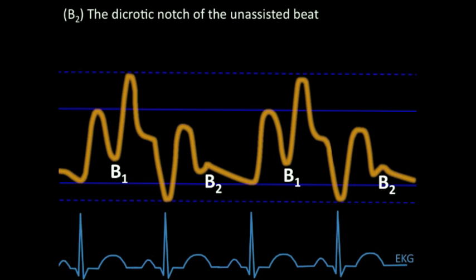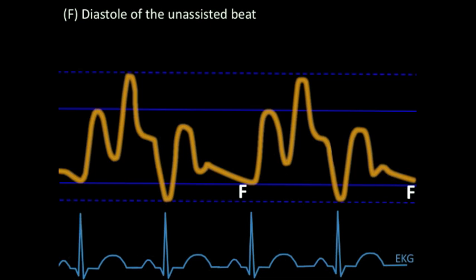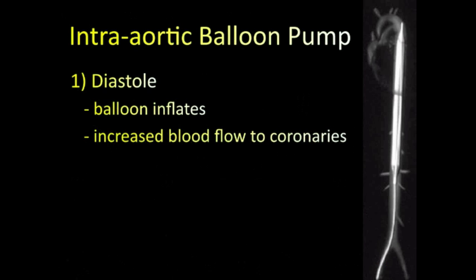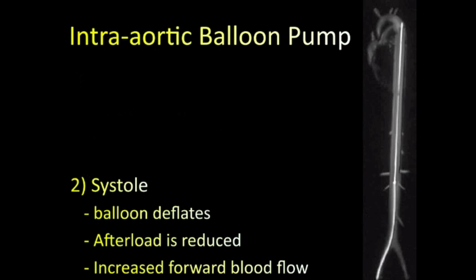The dicrotic notch of the unassisted beat occurs at a slightly lower aortic pressure than with the assisted beat, simply because the previous peak aortic pressure was lower — since E was lower, B2 will be lower. Lastly, diastole with the unassisted beat shows a higher aortic pressure than with the assisted beat. So to recap: in diastole, the balloon inflates causing increased retrograde blood flow and increased coronary perfusion; in systole, the balloon deflates resulting in decreased afterload.